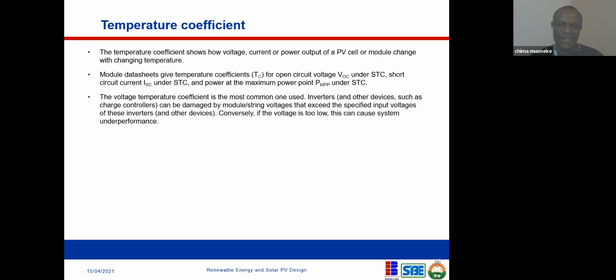Inverters and other devices such as charge controllers can be damaged by modules whose voltage exceeds the specified input voltage. If you exceed the required input voltage for your charge controller or your inverter, of course, you're most likely going to damage those electronic equipment. So that's why it's important that you look at your VOC, the open circuit voltage of your solar modules.